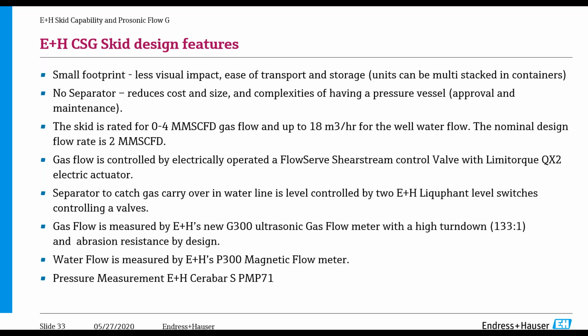Gas flow is measured by Endress+Hauser's new G300 ultrasonic gas flow meter. And another point I didn't mention earlier, but this flow meter has a very high turn down ratio, which is beneficial in the coal seam gas industry because the well typically has variable flow over its lifespan. So at the beginning, you normally see very high flow rates, it then drops down to some sort of stabilized flow, and then would drop down to even another level at the end of life.